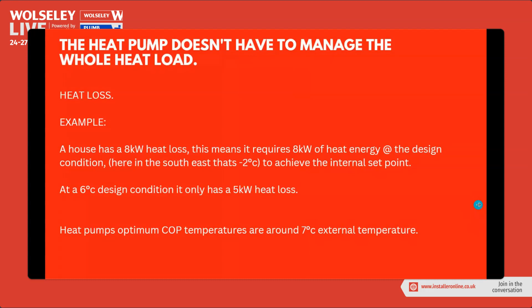So when that design condition or external temperature rises, you'll see there, at 6 degrees, we've only got 5 kilowatt heat loss. So that's where our heat pump can crack on and do the heating system. The optimum temperatures for heat pumps are around 6 to 7 degrees, so we can really get high efficiencies out of the unit. So when it's really cold and it's -2, stick with our trusty gas boiler. And then when it's a bit more mild and it's heat pump territory, we can use the really high efficiencies of the heat pump.